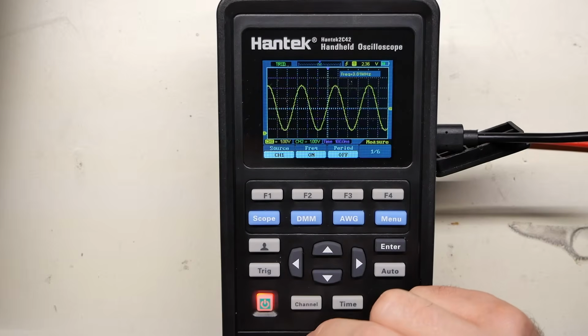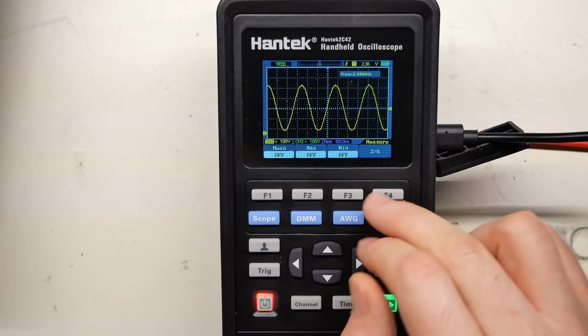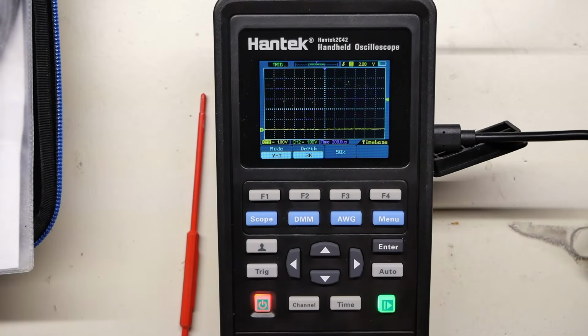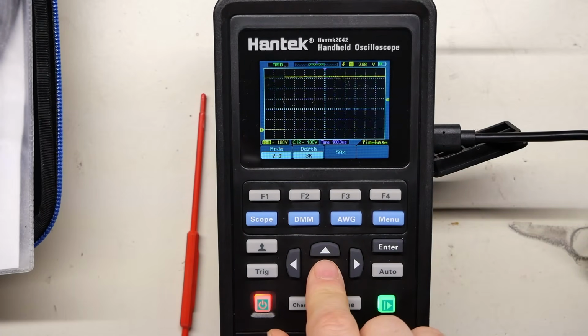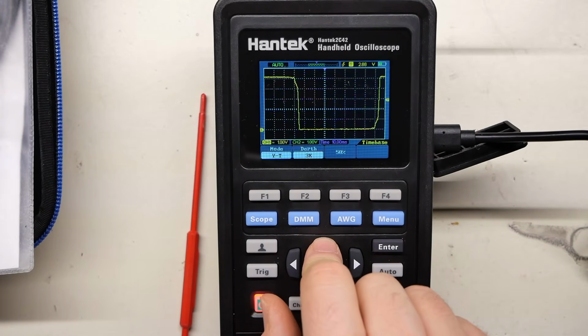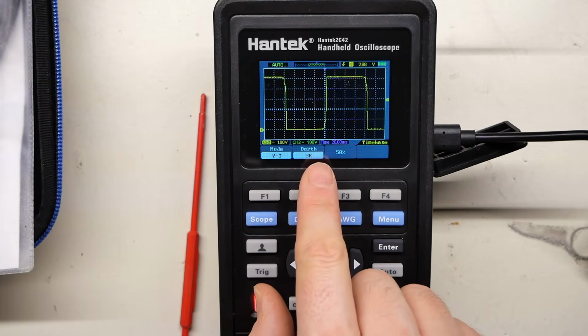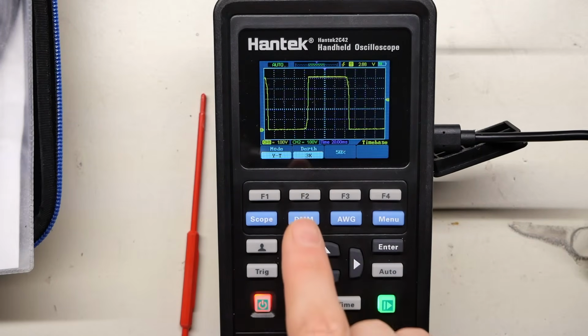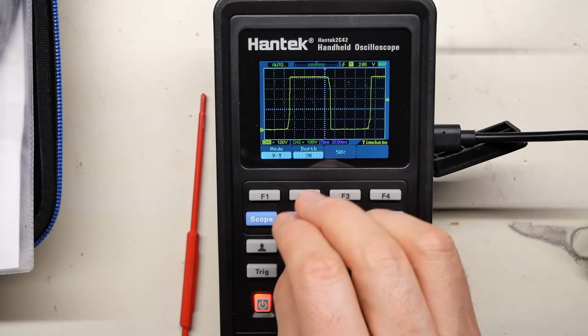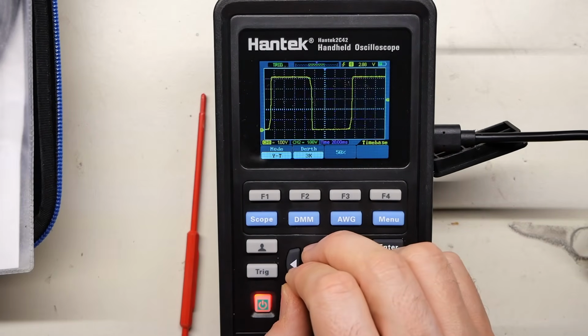I would really just like that frequency to be on there all the time, along with max. Those two things I'd like to see all the time. And here's a little bit of a trap for young players. So I'm looking at a 1 megahertz signal, and look how it's not doing anything that makes any sense, right? Now we're getting what looks like a square wave, but the time base is 20 milliseconds. So we're actually zoomed way out on the waveform.